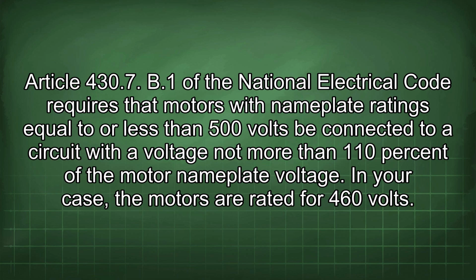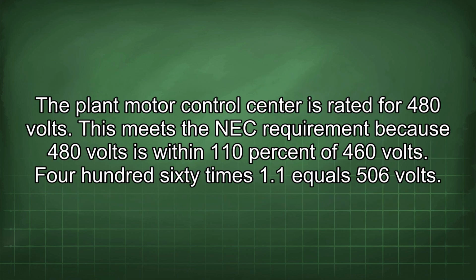In your case, the motors are rated for 460 volts. The plant motor control center is rated for 480 volts. This meets the NEC requirement because 480 volts is within 110% of 460 volts. 460 times 1.1 equals 506 volts.